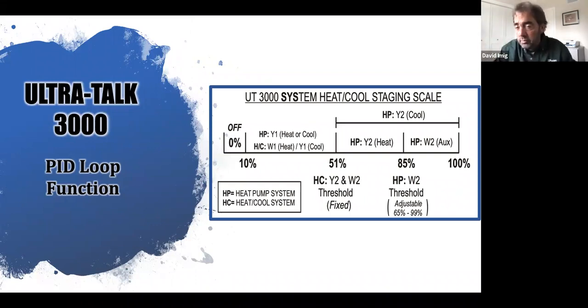Now, if I was in a heat pump operation, outdoor heat pump, I reached 51 and I did not meet my target temp of 112, I kick in second stage. At that point, I still keep going up until I see my target temp. I can go up 52, 53 in 22-second increments until, if at some point I get to 85% based on this particular setting, note in the default settings it said 95, and here we show 85. If I go up in 22-second increments to 85% and I have not reached my target temp, I bring on auxiliary, which is either my dual fuel and I drop Y, or I keep Y energized and supplement, one of the two. But that is the formula that determines how I stage in 2-stage equipment.